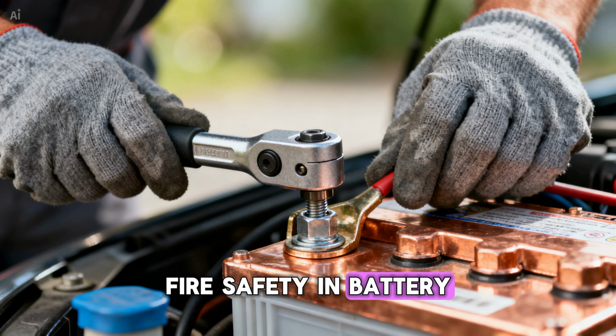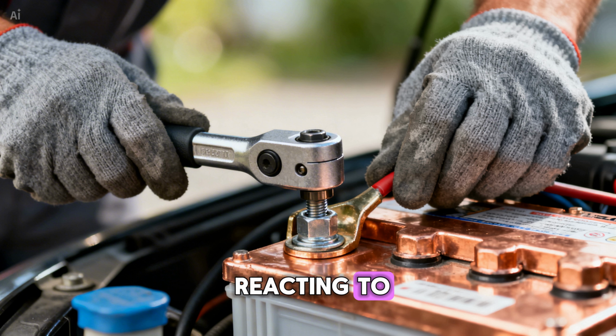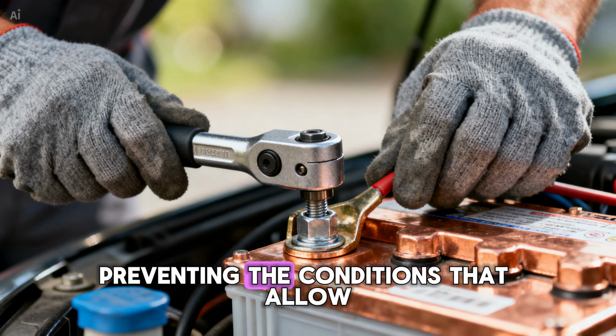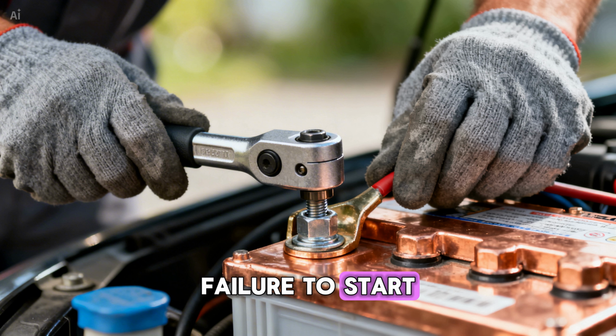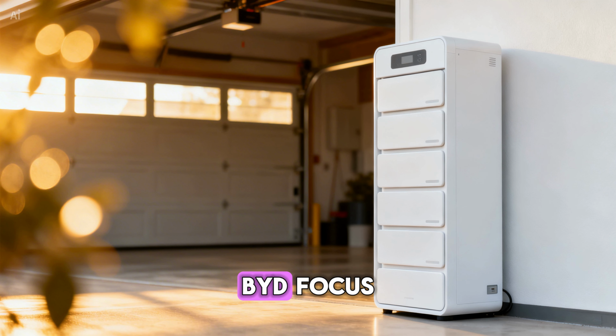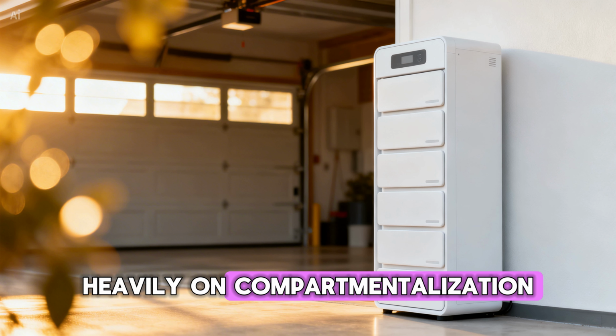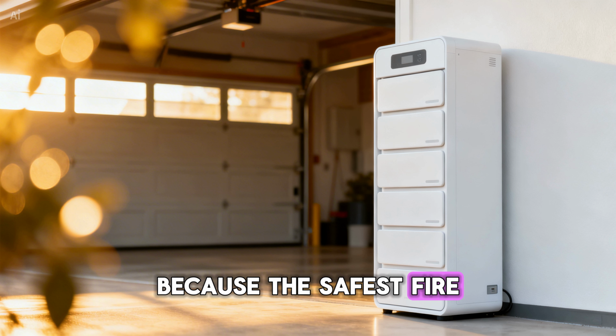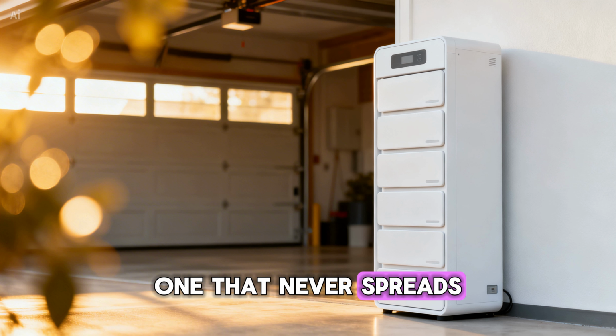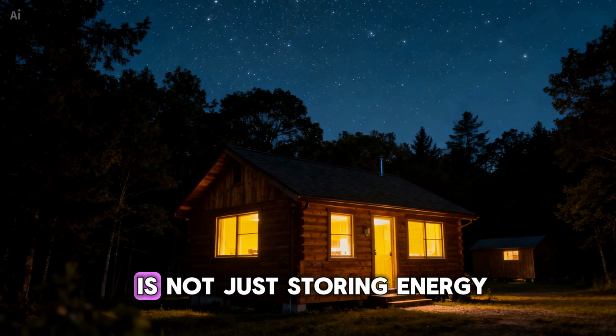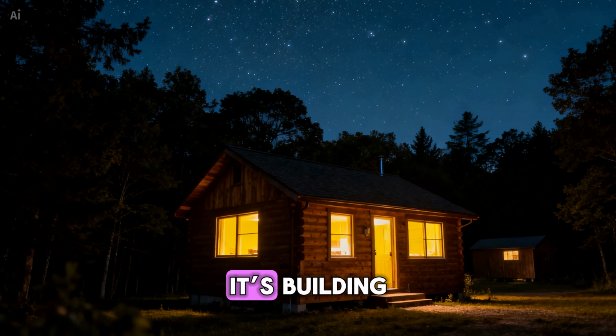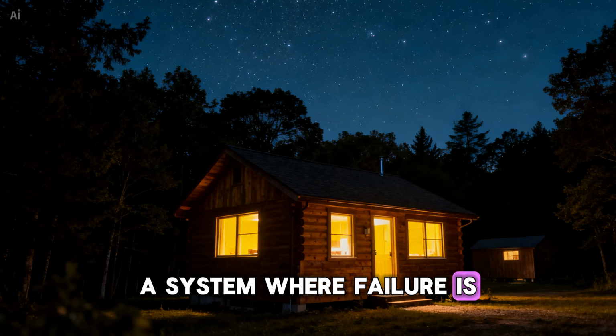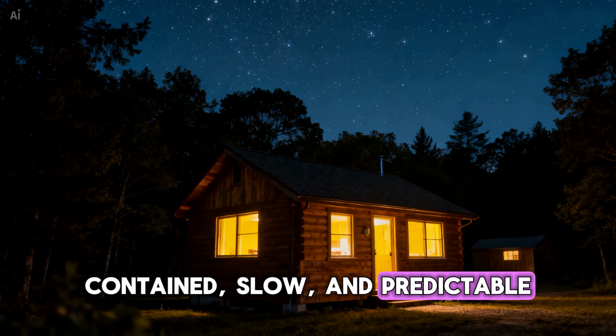Fire safety in battery banks is not about reacting to failure. It's about preventing the conditions that allow failure to start. Even brands like BYD focus heavily on compartmentalization, because the safest fire event is the one that never spreads. So the real goal is not just storing energy. It's building a system where failure is contained, slow, and predictable.